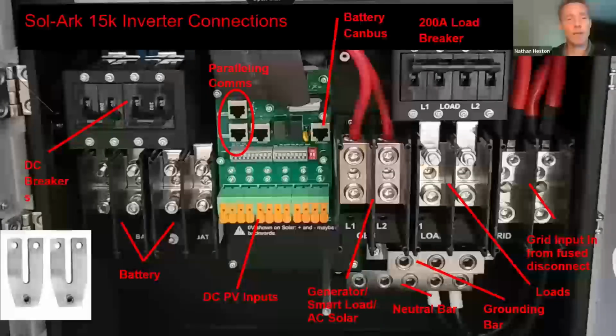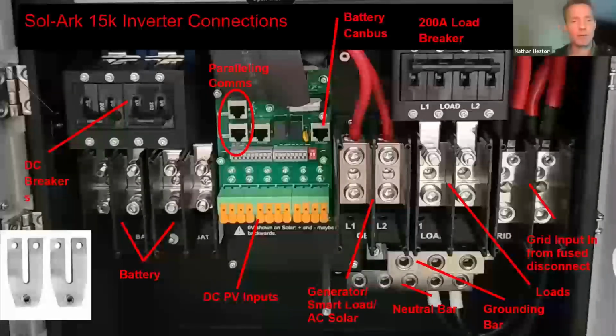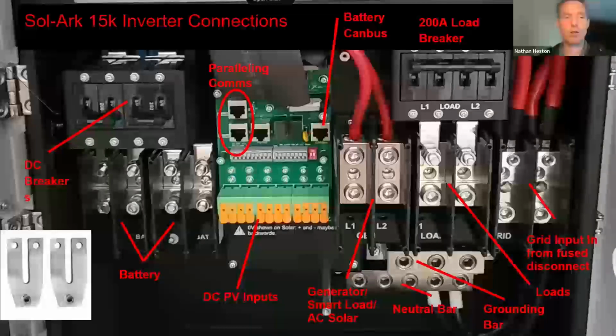On the left side of the screen, we've got the battery inputs. So you've got 2 independent breakers for your battery inputs, and they've done that so that you can run 2-aught wiring instead of being required to run 4-aught wiring. So if you have 2 individual leads coming from 2 battery banks, you can combine them at the inverter and run them through 2 2-aught connections. If, however, you would like to run just a single bank with a 4-aught connection, you can buy these bus bars that are made specifically for the Sol-Ark 15k and combine those connections so that you have one 4-aught connection coming in and you're not limited by a single 200 amp breaker.